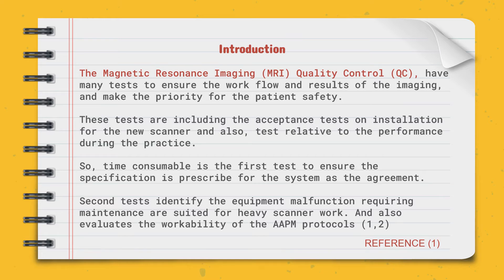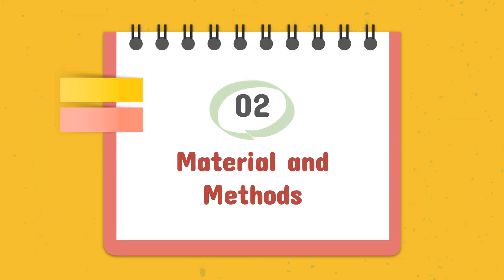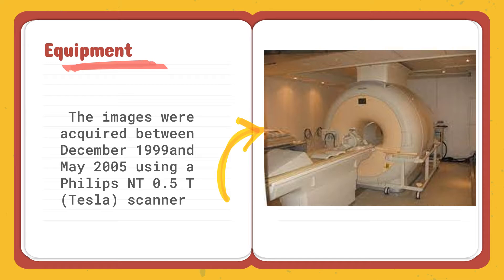We follow the workability of the protocol AAPM-102. For material and method used to ensure quality control of the MRI system: the study uses a Philips MRI with 0.5 Tesla. This study was conducted between 1999 and 2005.